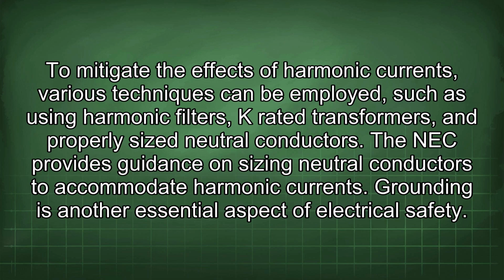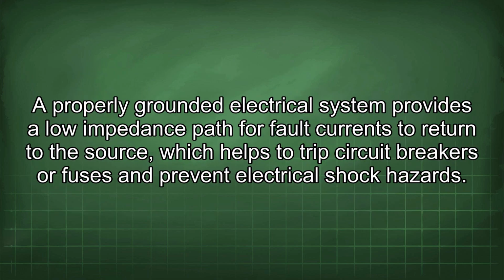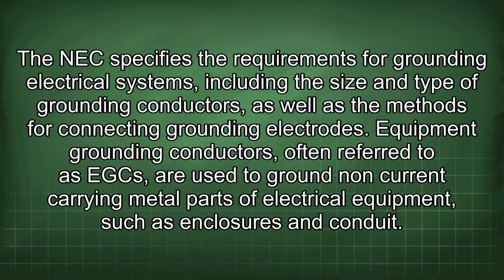Grounding is another essential aspect of electrical safety. A properly grounded electrical system provides a low impedance path for fault currents to return to the source, which helps to trip circuit breakers or fuses and prevent electrical shock hazards. The NEC specifies the requirements for grounding electrical systems, including the size and type of grounding conductors, as well as the methods for connecting grounding electrodes.